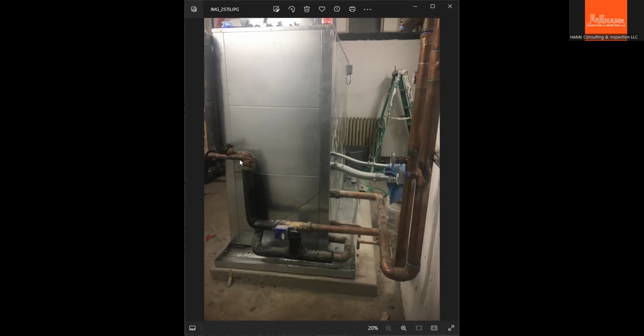So for that, this is another piece of information. It isn't really necessary to test the equipment during this kind of testing, because we're only testing the newly installed pipe outside the equipment. All this equipment has been pre-tested by the manufacturer. So they don't need to include it in the test. They need to isolate it from the new piping that we are testing.